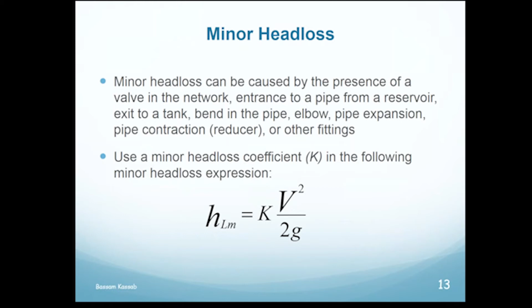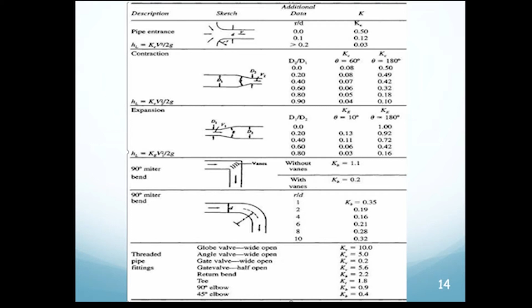And notice here, they talk about the valve wide open or half open. When the valve is wide open, you have less losses. K is smaller. When it's half open, you get more losses. K becomes larger. And even when you open it just a little bit, the K could become very huge. And that's why you cannot really neglect the minor loss in this case. The word minor, I consider it a misnomer. They call it minor, but it doesn't mean it's too small. It's just because it's localized. It happens in one location, like at the valve, unlike the friction loss, which happens throughout the length of the pipe, over thousands of feet or meters. But when we talk about minor loss, it happens in one location, like at the valve.